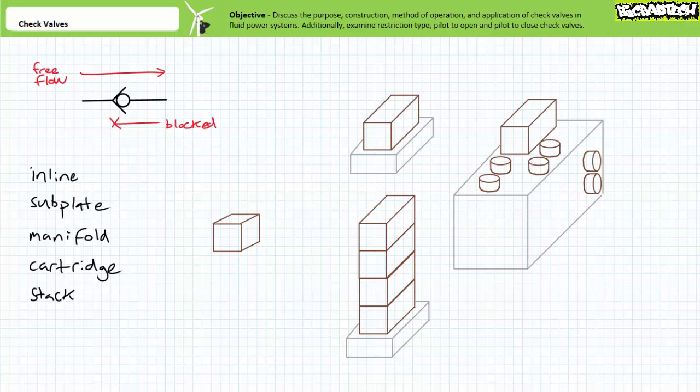Connections from a hydraulic power unit can be routed to a manifold containing a number of cartridge valves, then via flexible hoses or rigid pipes, fluid can be routed from the manifold to subplate mounted valves, a collection of stack valves mounted on a subplate, or other inline valves, all controlling the strength, speed, and direction of fluid power actuators.